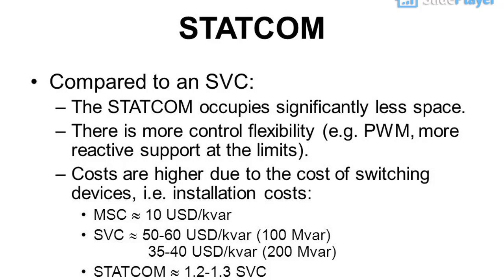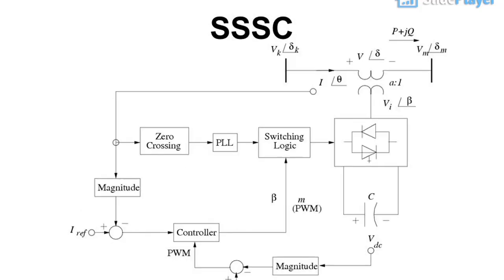Costs are higher due to the cost of switching devices, i.e., installation costs. MSC: ~10 USD/kVAr. SVC: 50–60 USD/kVAr (100 Mvar), 35–40 USD/kVAr (200 Mvar). STATCOM: 1.2–1.3 times SVC cost.